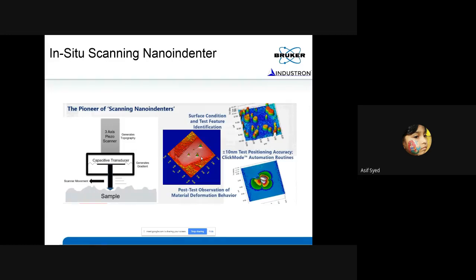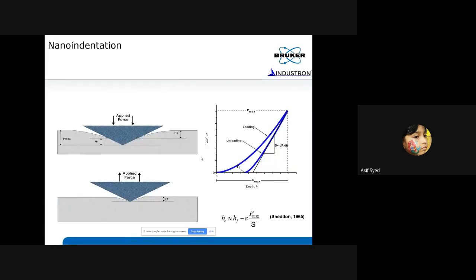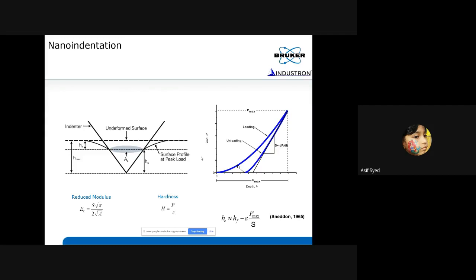And with that, I also mentioned that you can do load displacement curve, measure the penetration depth, measure the stiffness of the unloading curve. Once you know the stiffness of the unloading curve, you can measure the modulus of the material because by calibrating the tip, you can get the area of the tip as a function of depth. We call it the area function. And once you know the stiffness and the area of the indent that you did, you can calculate the modulus through this equation. And if you take the maximum load divided by the area of the indent, you measure a parameter called hardness, which is nothing but mean contact stress.